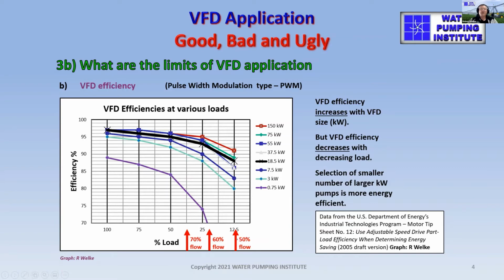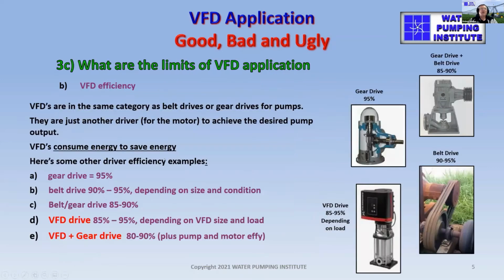So that's pretty much the limitations of your VFD as far as efficiency goes. If you're reducing the flow by 50%, you're actually down to 12.5% motor loading. And in those situations, you could be as low as only 90% efficiency with a VFD. So those magical power savings start to whittle away, and not just with the VFD efficiencies, but also with the pump efficiency itself. And that's the major thrust of what we'll look at today.